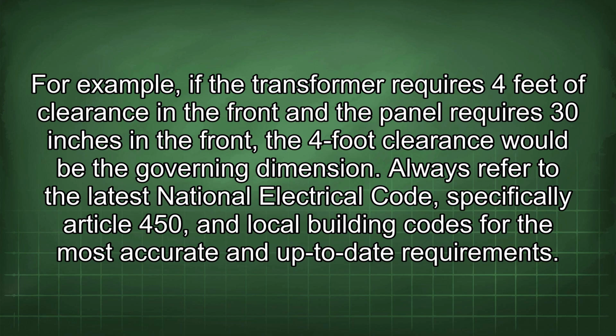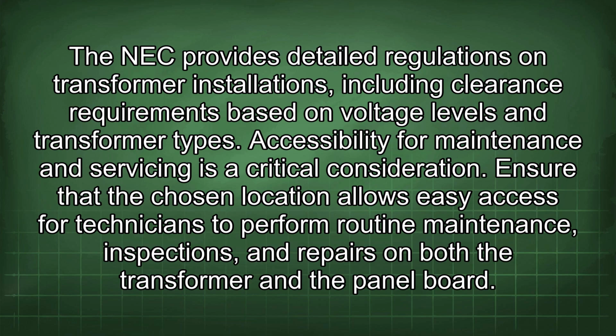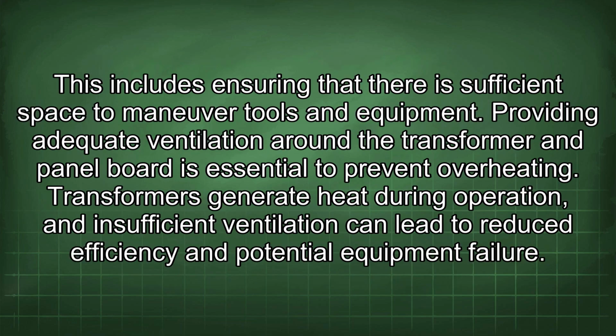Always refer to the latest National Electrical Code, specifically Article 450, and local building codes for the most accurate and up-to-date requirements. The NEC provides detailed regulations on transformer installations, including clearance requirements based on voltage levels and transformer types. Accessibility for maintenance and servicing is a critical consideration. Ensure that the chosen location allows easy access for technicians to perform routine maintenance, inspections, and repairs on both the transformer and the panel board. This includes ensuring that there is sufficient space to maneuver tools and equipment. Providing adequate ventilation around the transformer and panel board is essential to prevent overheating. Transformers generate heat during operation, and insufficient ventilation can lead to reduced efficiency and potential equipment failure.